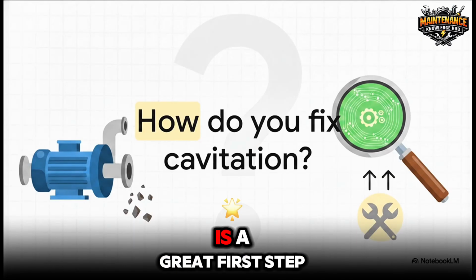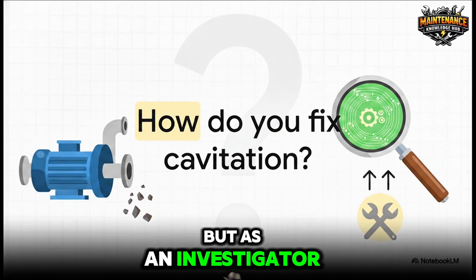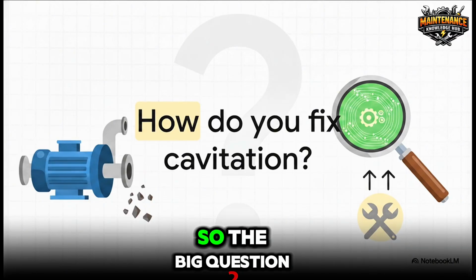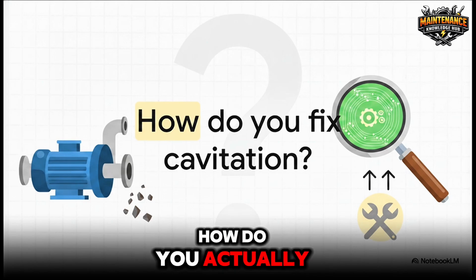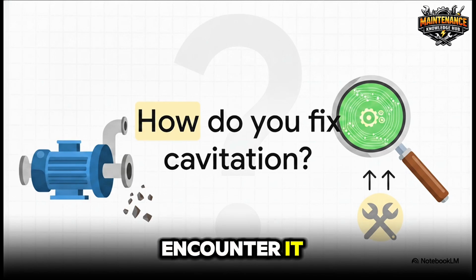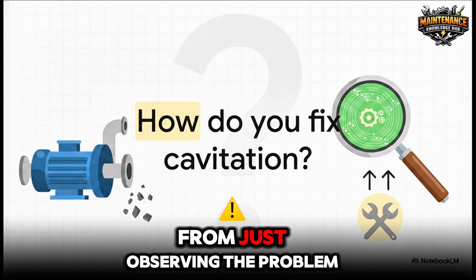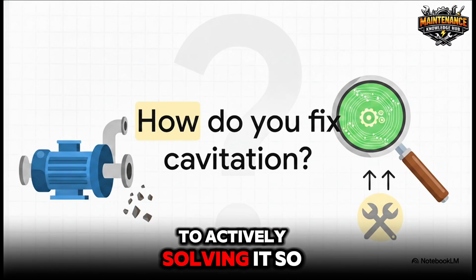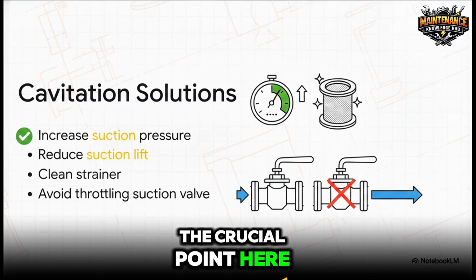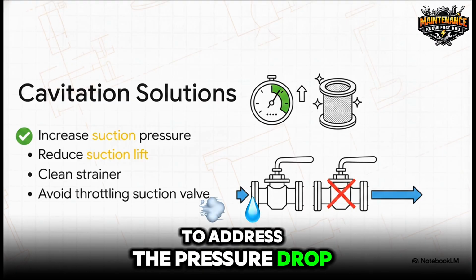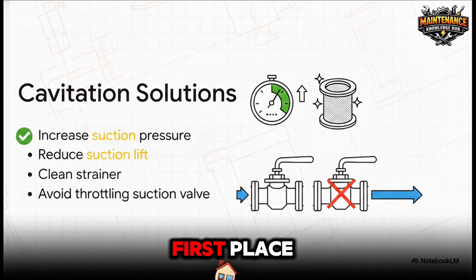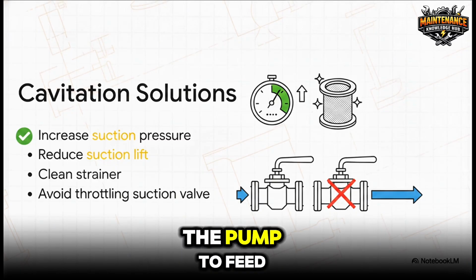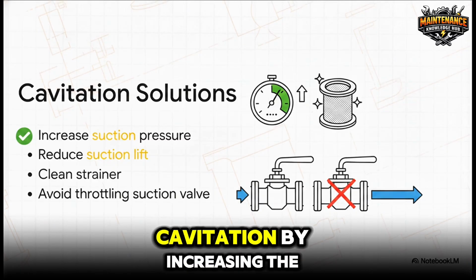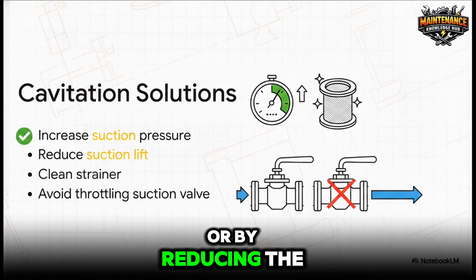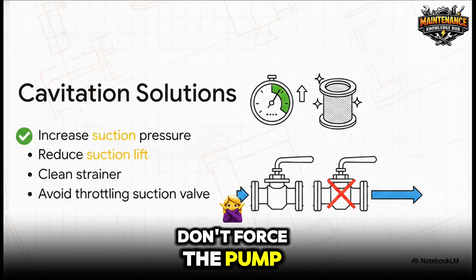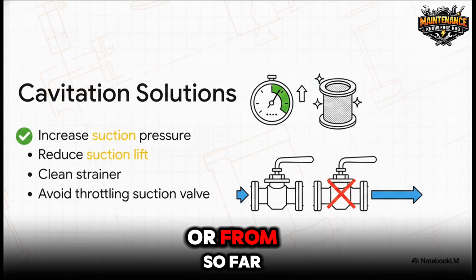Identifying that gravel sound is a great first step, but as an investigator, you're here to solve the case. So the big question, how do you actually fix cavitation when you encounter it? We really need to shift our mindset here from just observing the problem to actively solving it. So the crucial point here is that you have to address the pressure drop that is creating those destructive bubbles in the first place. You basically have to make it easier for the pump to feed. You can actually fix cavitation by increasing the suction pressure or by reducing the suction lift. That just means don't force the pump to pull the liquid from so deep down or from so far away.